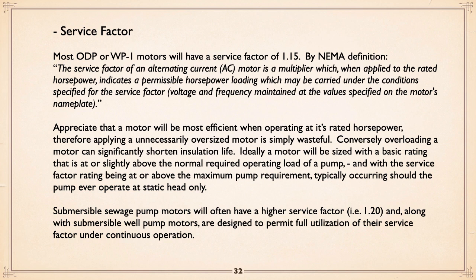Now, a motor will be its most efficient operating at its rated horsepower. 100 horse motor at 100 horse. Therefore, applying any unnecessarily oversized motor is simply wasteful. We actually, from an efficiency point of view, want that motor to be operating pretty close to its rating. Conversely, overloading a motor can significantly shorten life.